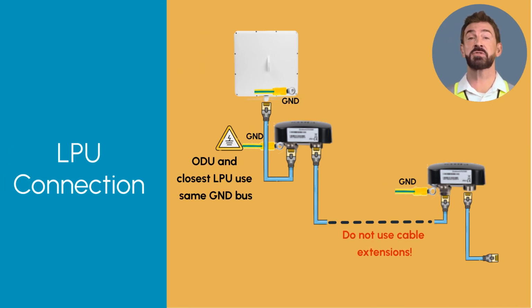This diagram illustrates the circuit between an outdoor unit, lightning protection unit, and the PoE. Pay close attention to the orientation of the lightning protection unit and its terminals. Ensure the ODU and the closest LPU use the same grounding bus. It is also important to note that the PoE solution itself must be properly grounded.